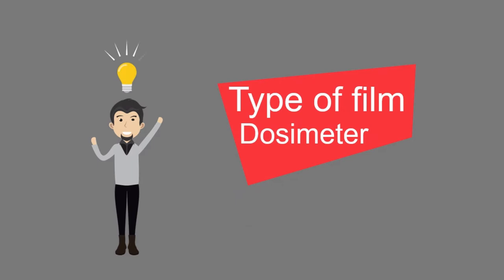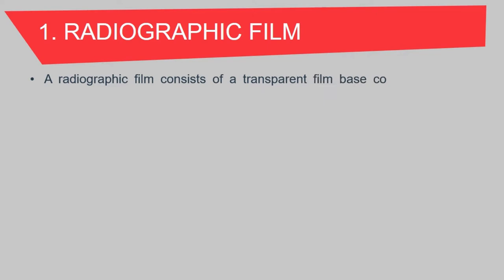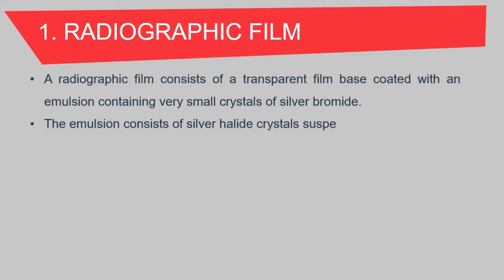Next is the type of film dosimeter. First is the radiographic film. A radiographic film consists of a transparent film base made out of cellulose acetate or polyester resin, coated with an emulsion containing very small crystals of silver bromide.